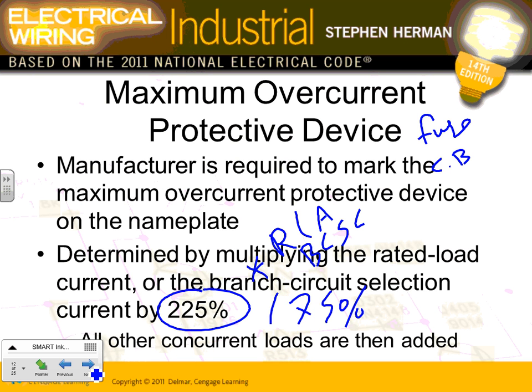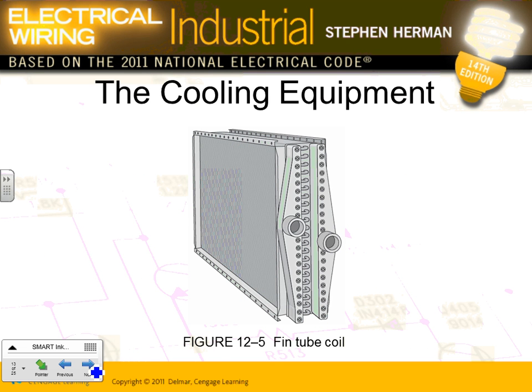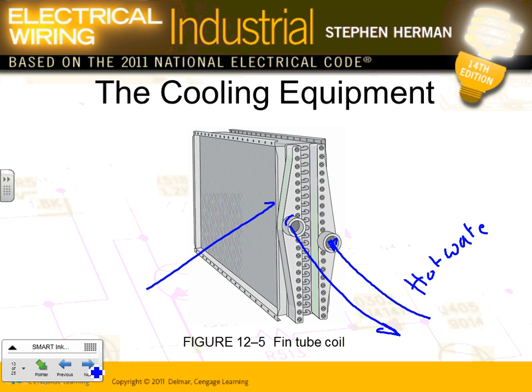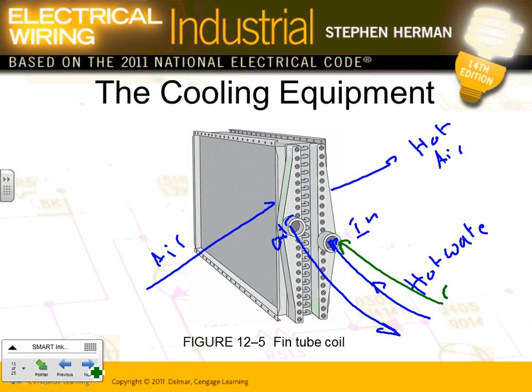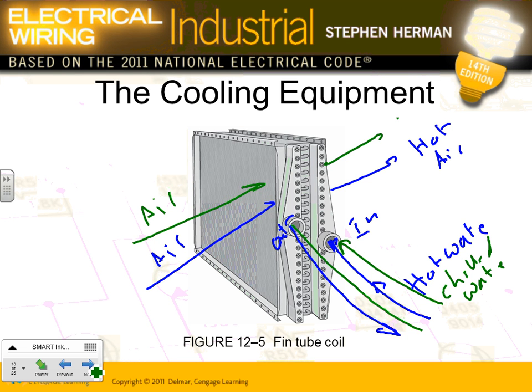Any comments, guys, about these? When we did the commercial project, if you remember, we went over this one too. Coil. Here's the coil, the typical coil. You bring hot water in here and blow air across it, and then the water goes back out here. This is the in and out, and you blow air into this. What are you going to get from the other side? Hot air. If the opposite is true, and you put chilled water here and bring it back to keep chilling it, and you blow air in it, what are you going to get out here? Cold air. That's how you get the hot and the cold in any building.